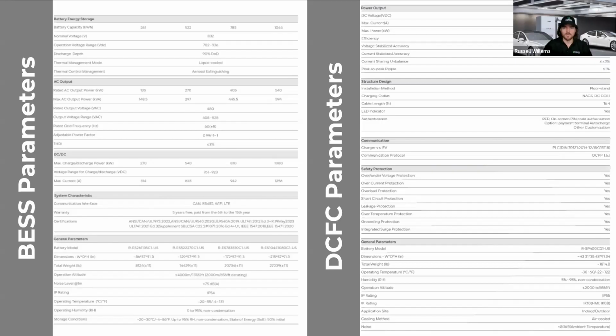To dig into these a little bit more, on the right side here you can see all of the DC fast charger parameters. So this is where you're going to see our max power. I know it's small here, so I apologize, but our max power output of 400 kilowatts, as I had mentioned, and that's paired with a max current of 400 amps, and that's when we're at that high enough voltage of 1,000 volts. So that kind of math is pretty straightforward there in terms of how you get to that 400 kilowatt power output. It's a very efficient system, round trip efficiency of around 97%, and very stable, capable of using peak shaving as well as whatever of your energy management systems that you want to use, all kind of integrate to form this production here and to get this much power out as needed.